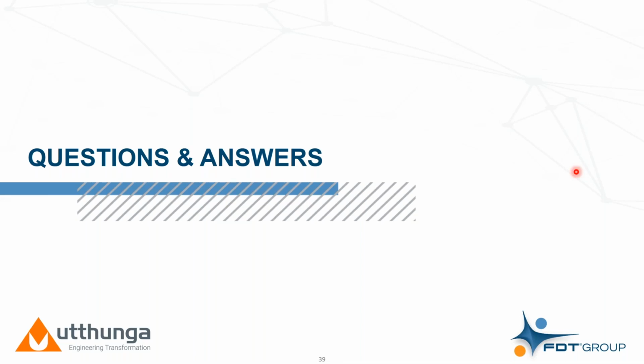And a very related question, Smitha, that I might as well take right away is, will FDT2 communication DTMs work with an FDT3 server? And the answer is, if there is not a need for a graphical user interface, that's generally a workable scenario. We actually did a fair amount of the testing that way ourselves early on with the common components. So as long as you don't have the need for a graphical user interface from the server to support that communications DTM, that should be a workable scenario. Obviously needs to be tested, but it's quite plausible.